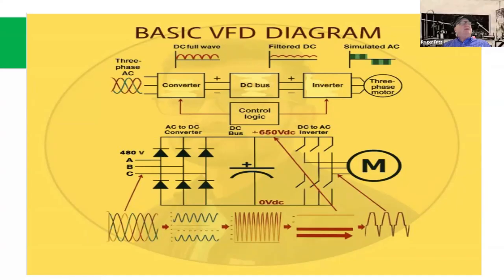PWM IGBT drives. What it typically does is convert the AC to DC with a diode front end. Then it has a DC bus circuit, and there are big electrolytic capacitors in here that create about 650 to 700 volts DC inside the drive unit. From that, they use the inverter sections, which are basically IGBT transistors, to fire these PWMs out to the motor, and then it controls the motor speed.